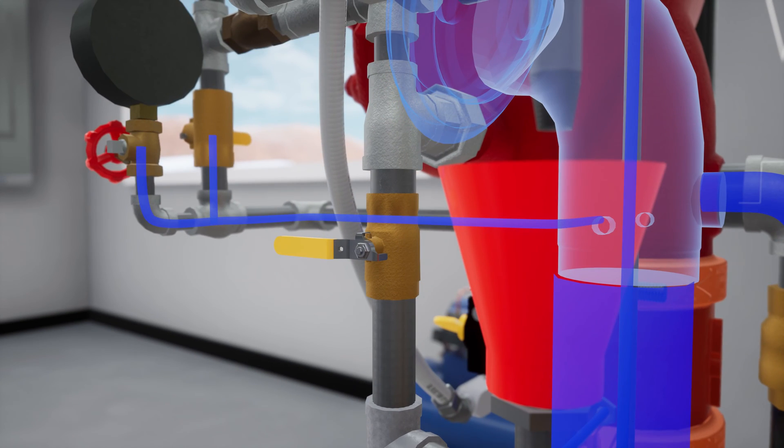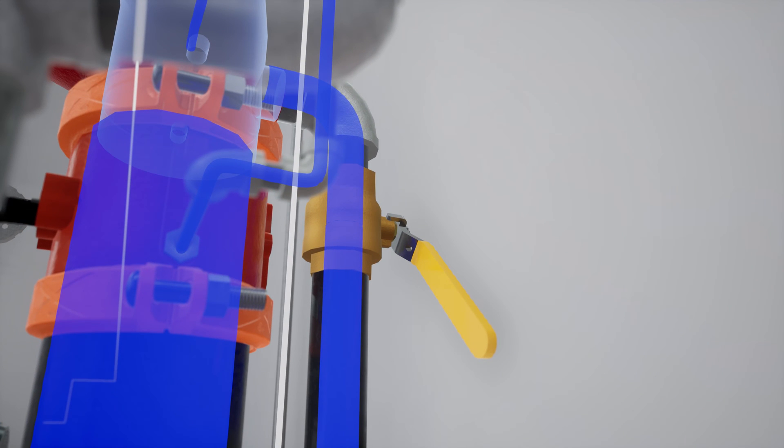Open the auxiliary drain and verify that there is no water flow. Close the auxiliary drain. Once flow has been established, close the flow test valve.